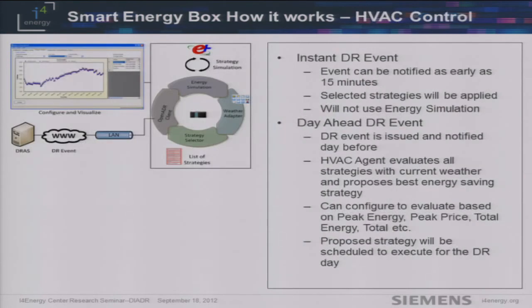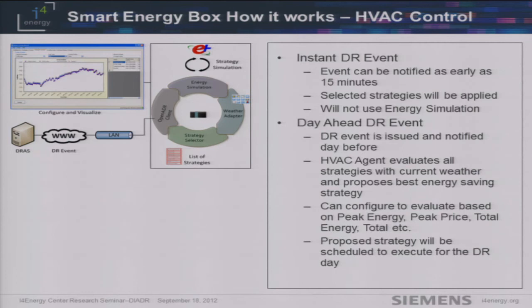If you have an instant DR event, we can start shedding as early as 15 minutes. During an instant event with only 15 minutes available, it's not going to evaluate energy strategies because there isn't enough time for HVAC analysis. In the case of a day-ahead DR event, it can evaluate all strategies and select the best one — configured to evaluate based on peak energy, peak load, or peak price, depending on the settings.